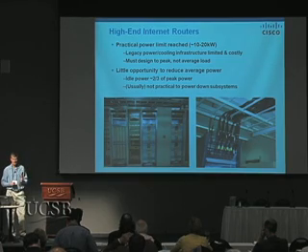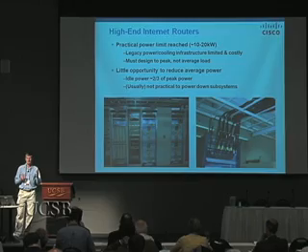There's little opportunity to reduce average power on these systems, because the core internet traffic has such high multiplexing that the difference between peak and valley load doesn't give enough opportunity to turn components off. It's very difficult to turn system components off and save power when trying to be carrier class — with 911 calls going through, needing 99.999% uptime with redundant parts. We are looking for opportunities but have not yet found success in saving power that way.